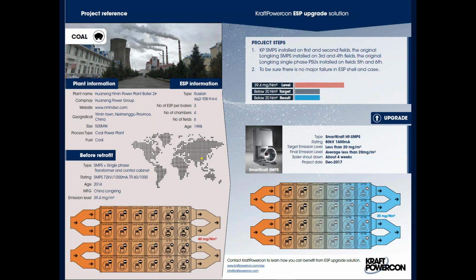They had 39.4 milligrams per normal cubic meter, which was above their limit, so they were taking derates—operating at about 0.04 or 0.05 pounds per million BTU. The target was 20 milligrams per normal cubic meter, and we were able to achieve that just by putting in a tier 2 power supply, which is what Kraft Powercon offers. This gave them the reliability, and when we wanted 80 kV, 1600 milliamps, it produced that.